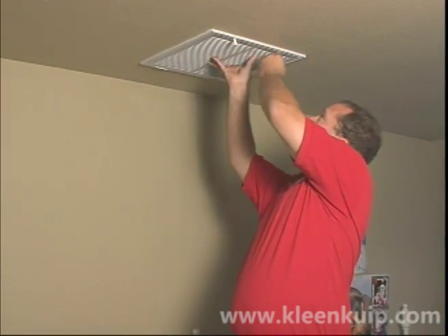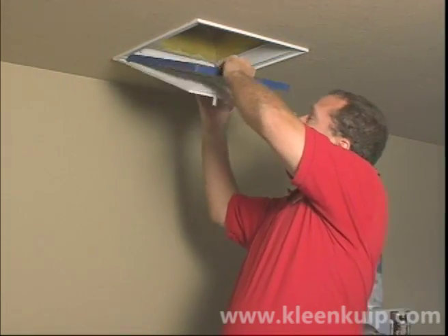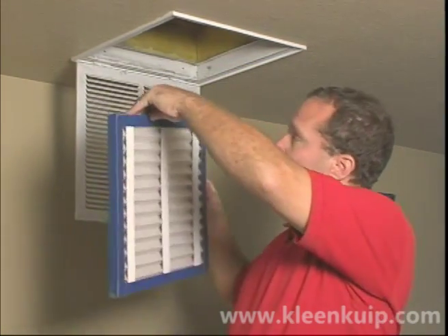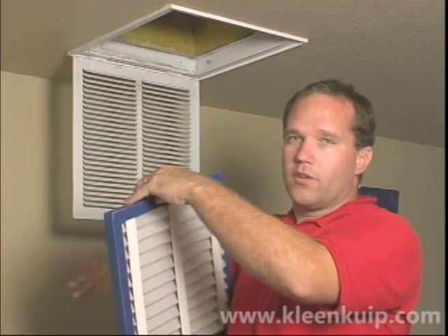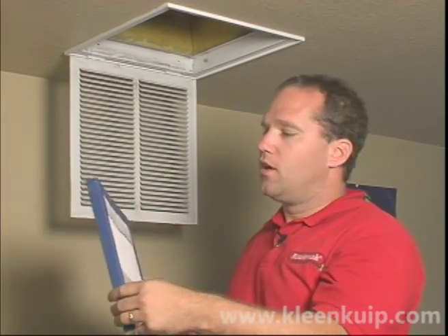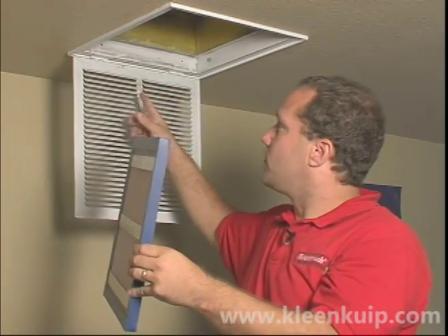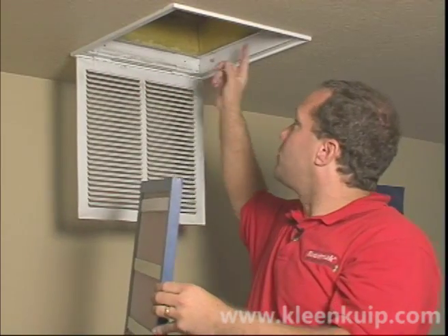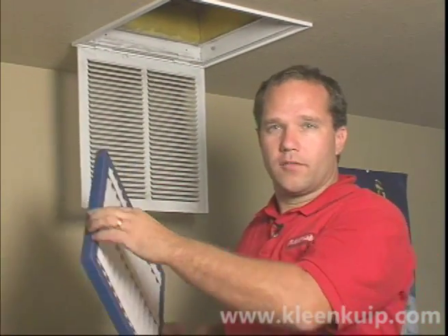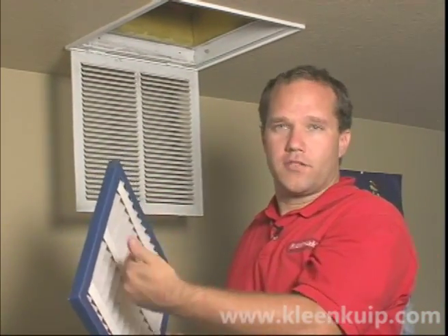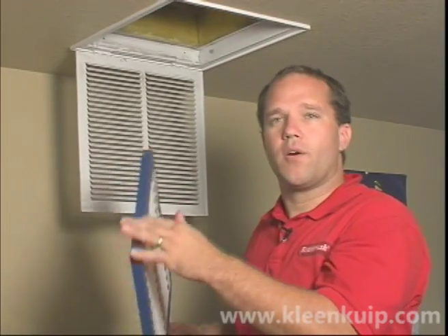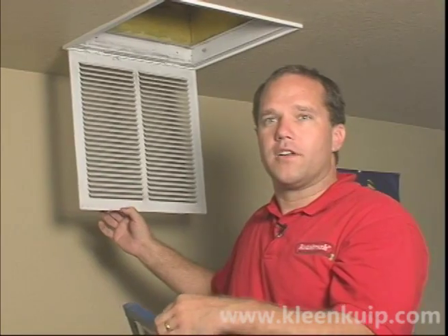And right here we have a return grill, which you're going to have either filtration systems in the ceilings or the walls or at the unit. This home here has them all in the ceilings and the walls, and you can see the bypass that you have here, which can be a symptom of the customer not changing out their filtration system, so you need to talk with them and see how often they change it. And typically you're going to have fewer returns than you will supplies in a home.